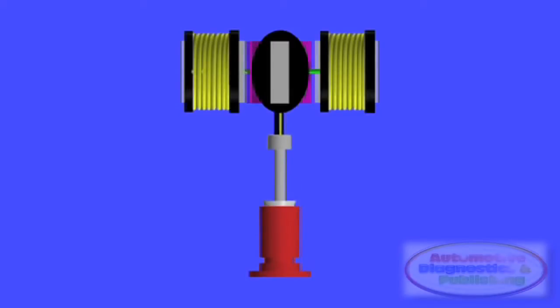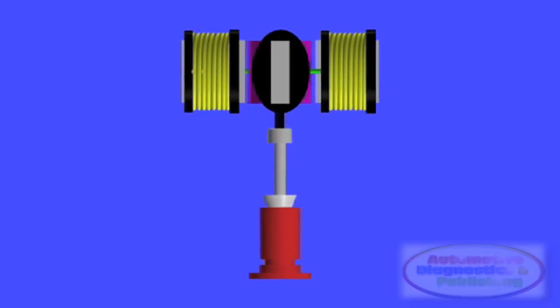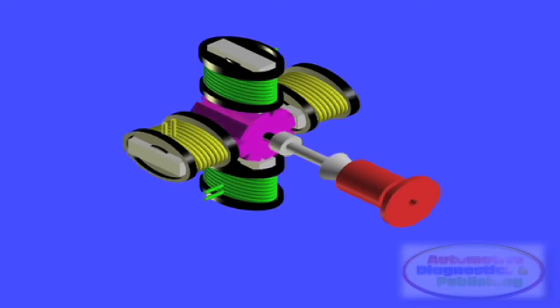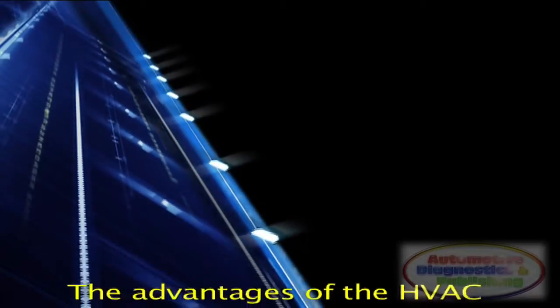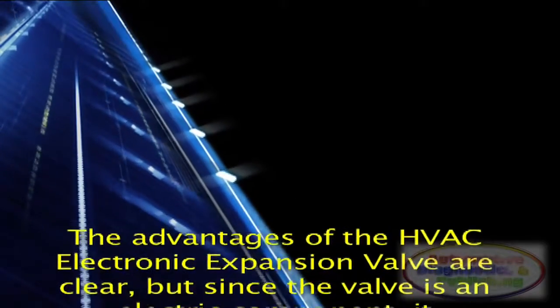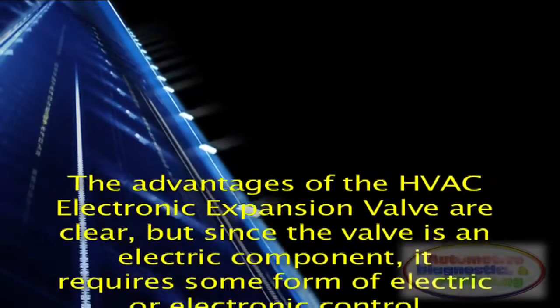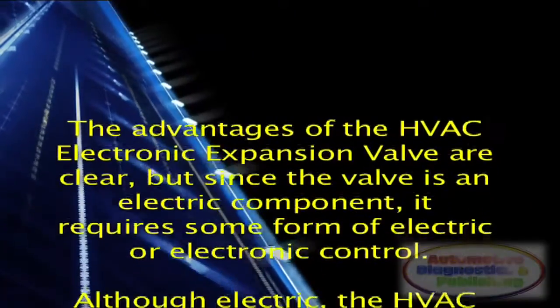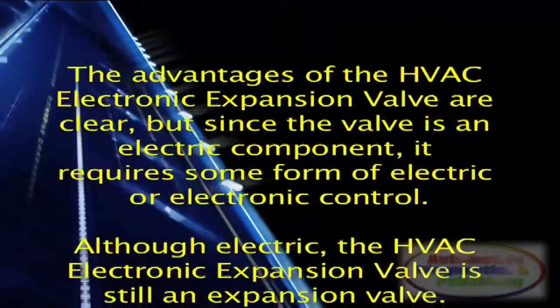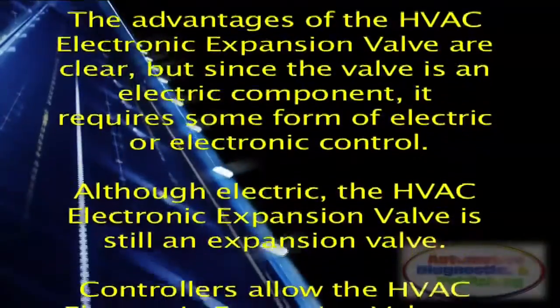In addition, flash gas in the liquid line is less damaging to the operation of the system, because the relatively large port and large stroke of the HVAC electronic expansion valve allows it to open wide, purge the flash gas, and then re-establish the desired superheat. The advantages of the HVAC electronic expansion valve are clear, but since the valve is an electric component, it requires some form of electric or electronic control. Although electric, the HVAC electronic expansion valve is still an expansion valve.